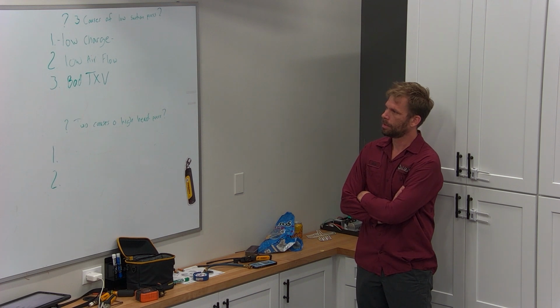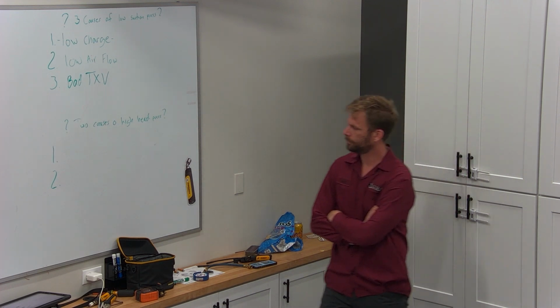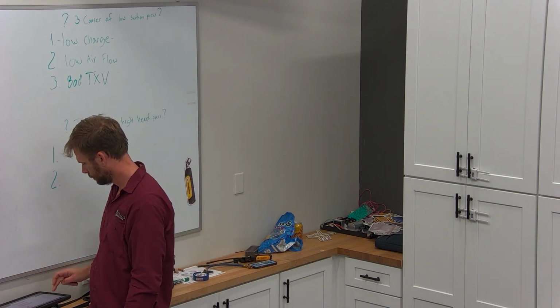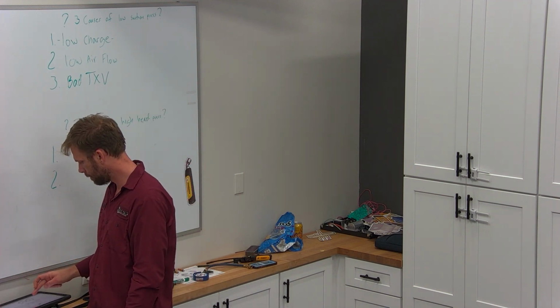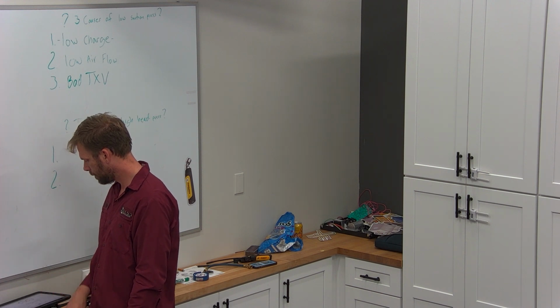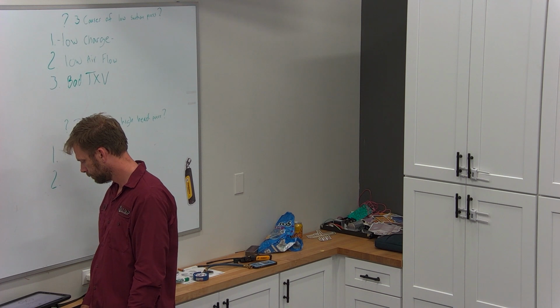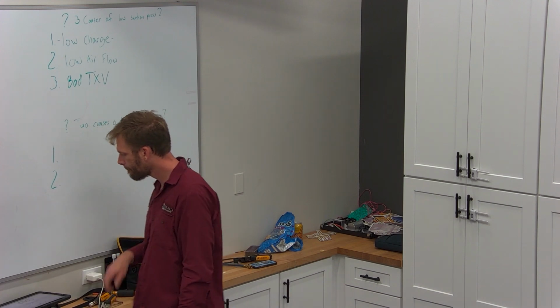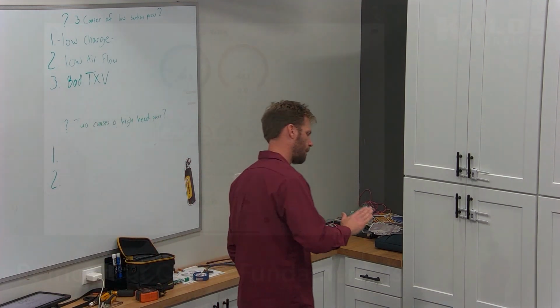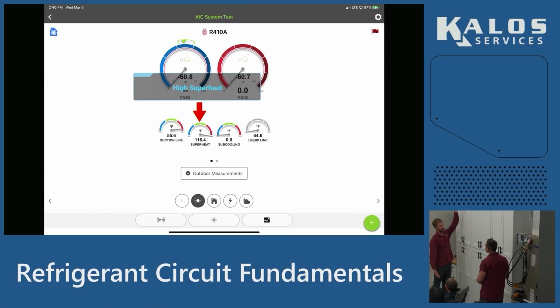Well, we are going to. But you can see, I've created a liquid line restriction, not necessarily a bad TXV. All you can see is the line temperatures anyway. You can see how my suction line is starting to climb and climb and climb. If we looked at the pressure, we would see that the pressure is low, so I have a high superheat right now because I'm starving my coil of refrigerant. You'll watch the suction line. It's still the same amount of heat coming into that coil with airflow, but now less refrigerant. So the heat is boiling it quicker and bringing that temperature up higher, higher superheat.